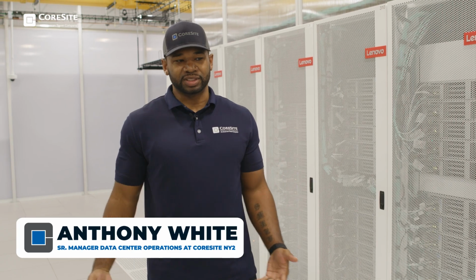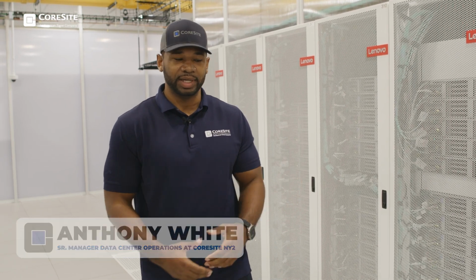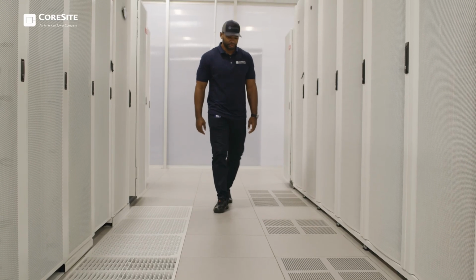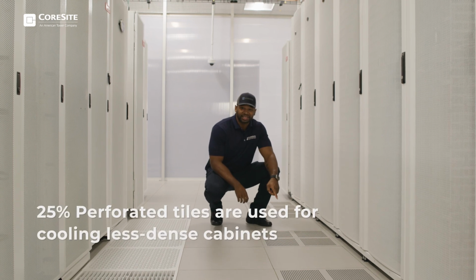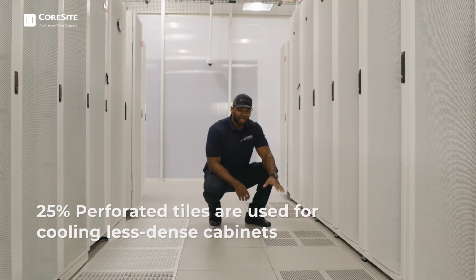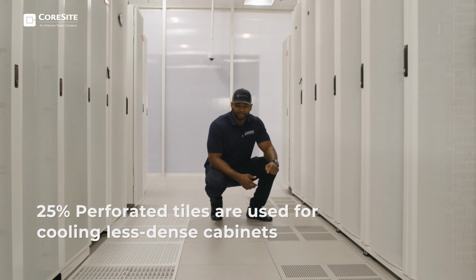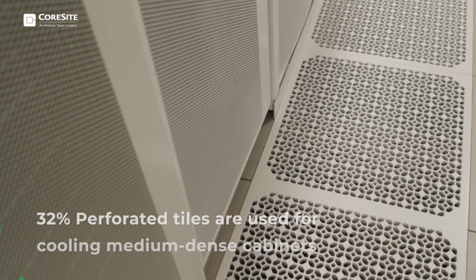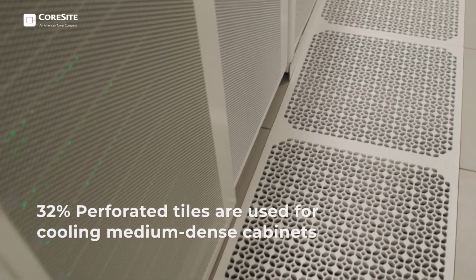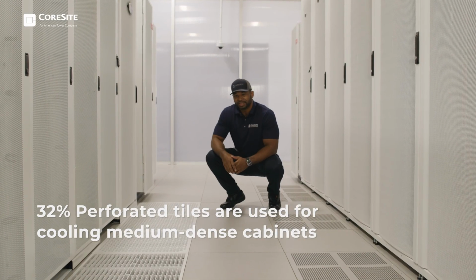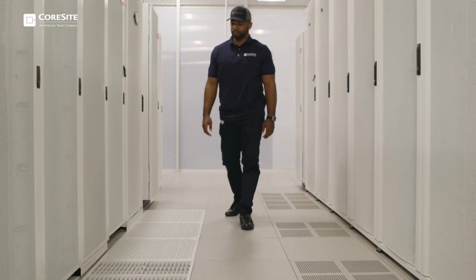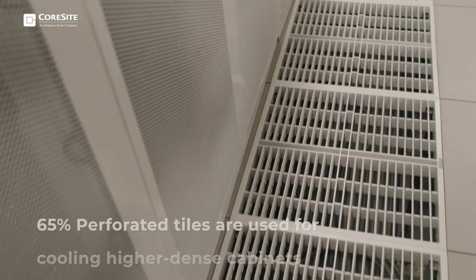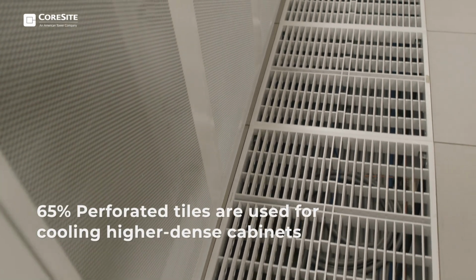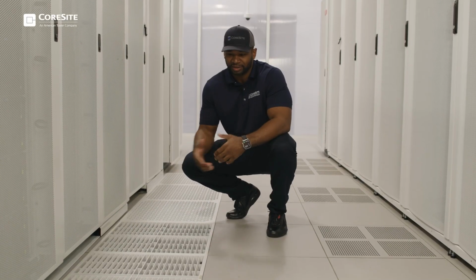That void allows us to deliver cold air exactly where we need it, through these perforated tiles. This perforated tile is 25% open, which allows us to cool a less dense cabinet. This tile here is 32% perforated, which allows us to cool the medium dense cabinet. This tile here is 65% perforated, which allows us to cool the higher dense cabinets.